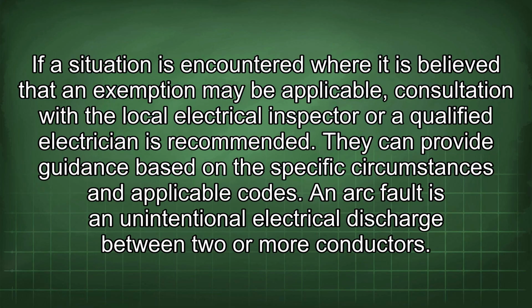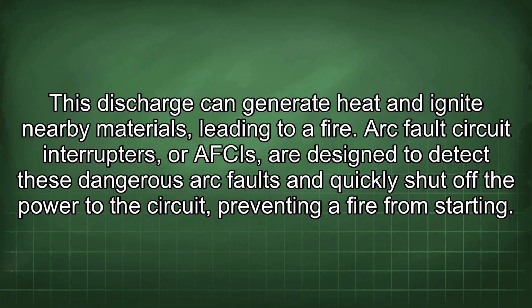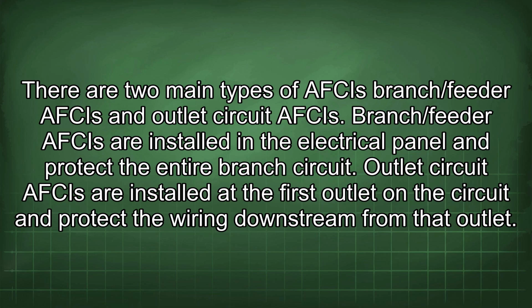An arc fault is an unintentional electrical discharge between two or more conductors. This discharge can generate heat and ignite nearby materials, leading to a fire. Arc fault circuit interrupters, or AFCIs, are designed to detect these dangerous arc faults and quickly shut off the power to the circuit, preventing a fire from starting. There are two main types of AFCIs: branch/feeder AFCIs and outlet circuit AFCIs. Branch/feeder AFCIs are installed in the electrical panel and protect the entire branch circuit. Outlet circuit AFCIs are installed at the first outlet in the circuit and protect the wiring downstream from that outlet.